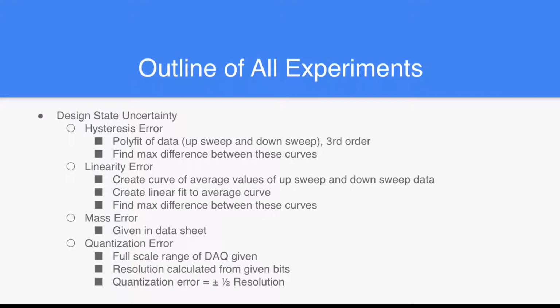Our design stage uncertainty consisted of 4 major parts. For the hysteresis error, first we did a polyfit of the data as we added 50 grams, and then the data as we took away 50 grams, and we fit those with third-order polynomials, and then we found the max difference between those curves. For the linearity error, we created a curve of all the average values of when we added 50 grams and when we took away 50 grams. We created a linear fit to that, and then we found the max difference between those two.